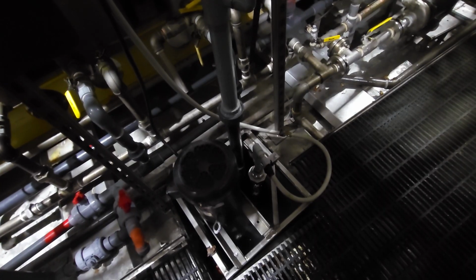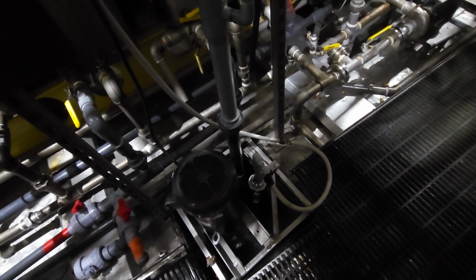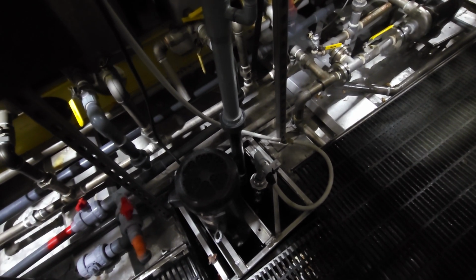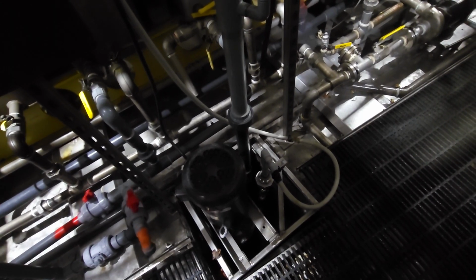So always check them when you walk by them. Make sure they look like they're all right. I even trigger it once in a while by pulling that middle float up and just see it pumps out. And they do spray, as you can see, but this one's working great. I checked the speed. Yeah, that pumped out nice and quick. But yep, that's the way to trigger it.